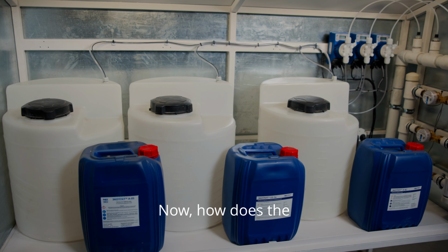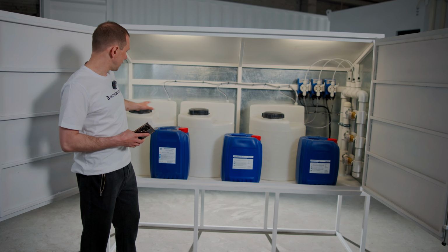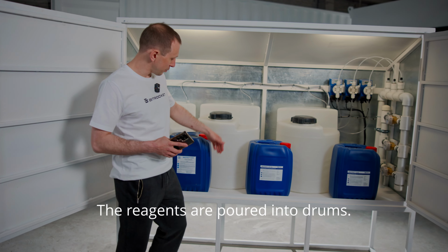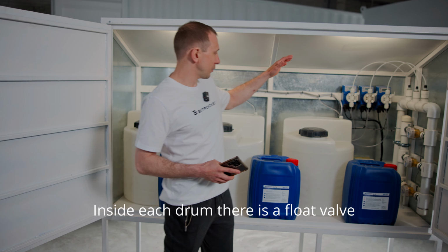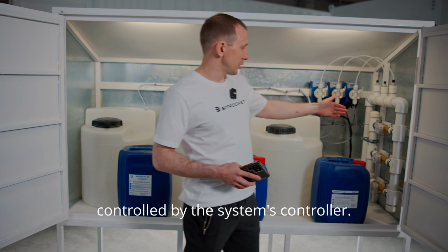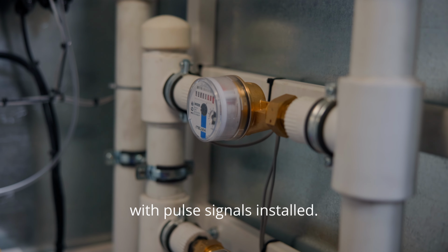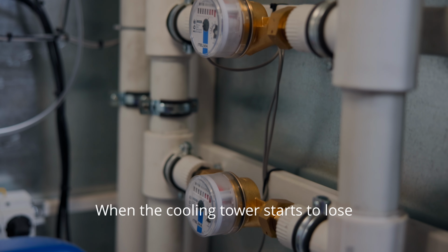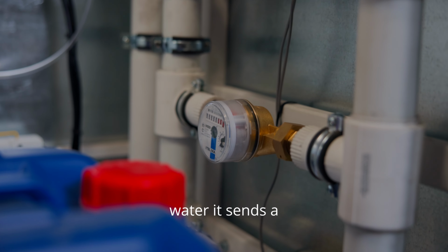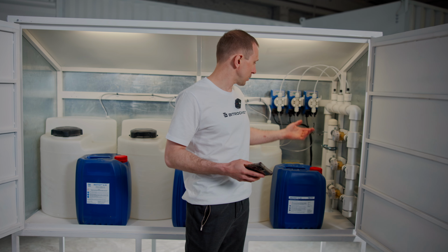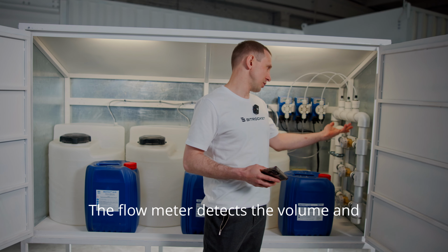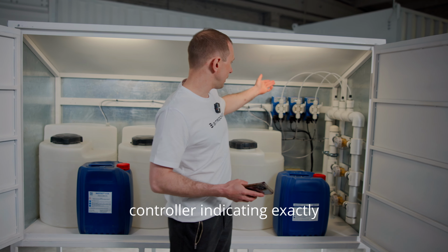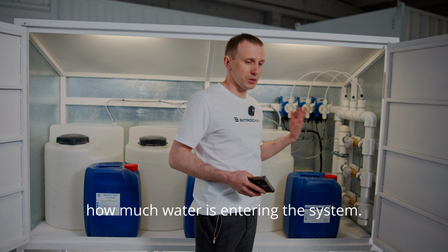Now, how does the system operate in practice? The reagents are poured into drums. Inside each drum, there is a float valve controlled by the system's controller. And here are flow meters with pulse signals installed. When the cooling tower starts to lose water, it sends a signal to begin refilling.